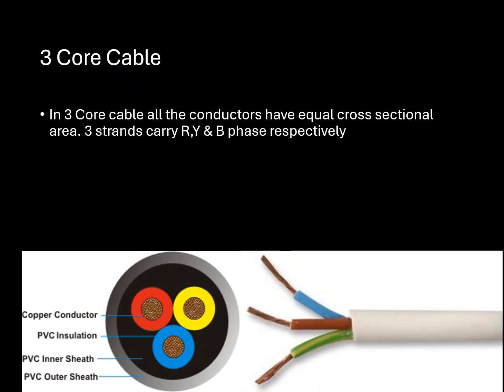The cables can be single core, twin core, or three core. In three core cable, all the conductors have equal cross-sectional area. These three are R, Y, and B. They have equal area. This one, and this one. See the conductor portion. This, and this. Now here, the inside is copper conductor or it may be aluminum. The blue exterior portion shows PVC insulation. This is PVC inner sheath. This is sheathing all around, and PVC outer sheath is this.